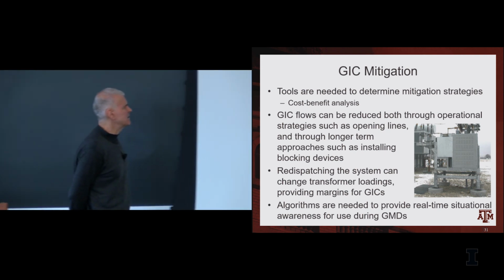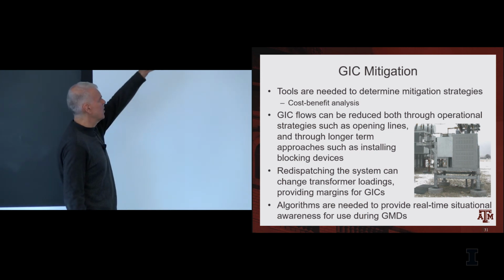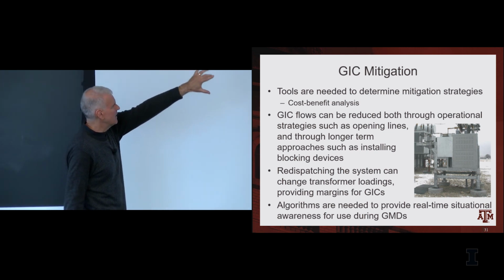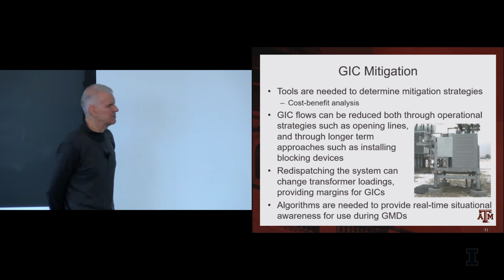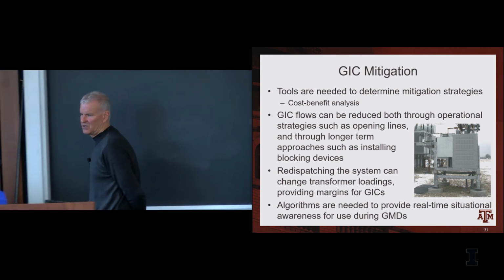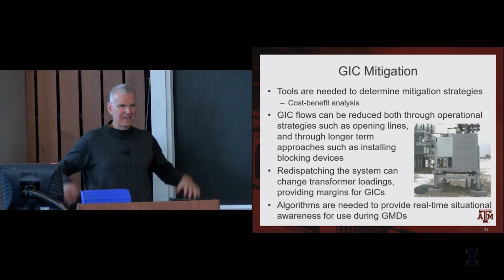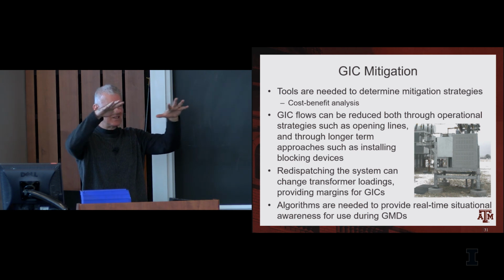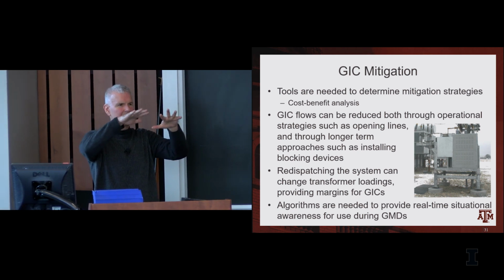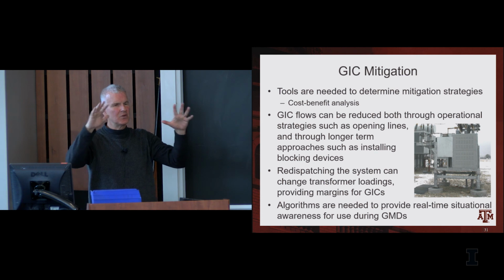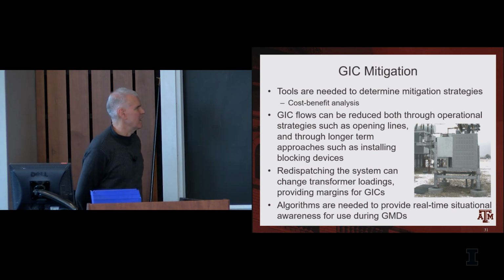One device that could be installed is what's called a GIC blocking device. That's a picture of a GIC blocking device installed in a substation in northern Wisconsin. The GIC blocking devices block these geomagnetically induced currents from getting into the ground, and when you do that you can potentially reduce their magnitudes.